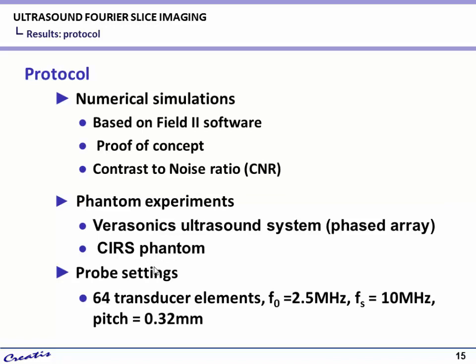Here I will show some results. We did numerical simulations and experiments to validate our method. The numerical simulations are based on Field II software, used to prove the algorithm and measure the contrast-to-noise ratio. The experiments use a Verasonics system with a phased array. Both use the same settings: 64 transducer elements, 2.5 MHz central frequency, 10 MHz sampling frequency, and pitch of 0.32 millimeters.